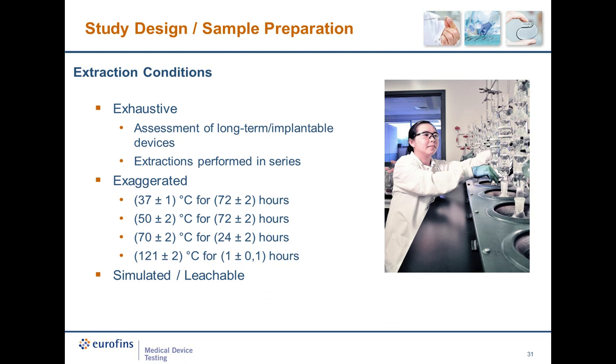Exaggerated extractions expose the device to conditions at least as and typically harsher than clinical use. The standard provides the four different conditions listed and also states that other conditions can be used provided that the sponsor provides justification. Important to note, the FDA does not consider 37C to be exaggerated, and there should be justification if this condition is used. Both exhaustive and exaggerated conditions provide a worst-case extractables profile. Exposing the medical device to worst-case clinical use conditions is the final possibility, which is considered a simulation or leachable study. Typically, a simulation study or leachable study is performed when the composition of the device does not allow for exaggerated conditions, or it is performed in conjunction with or after an exaggerated study based on the assessment of the exaggerated study.